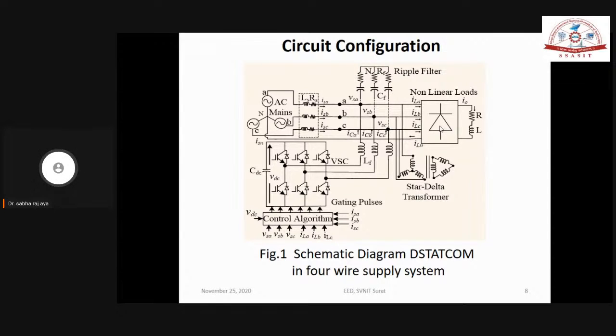If the load is balanced, in that case we are not going to observe any neutral current in both wires. If the load becomes unbalanced, where some phase has 50% load, some maybe 40%, some maybe 70%, then you are going to observe unbalancing in the whole three-phase load section. Now, due to that, we are going to observe neutral current in both wires. Okay. How much? In normal condition, neutral current is equal to the load neutral current; both are equal in normal condition.